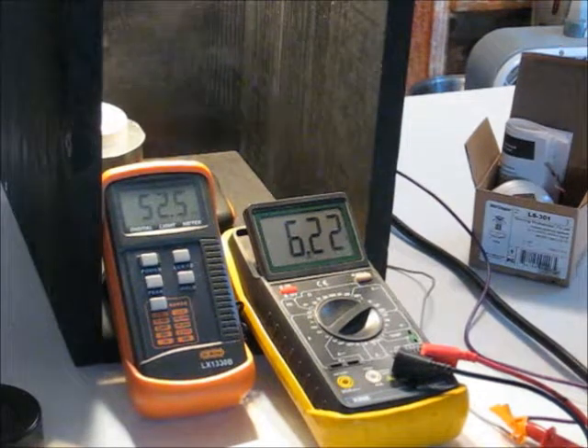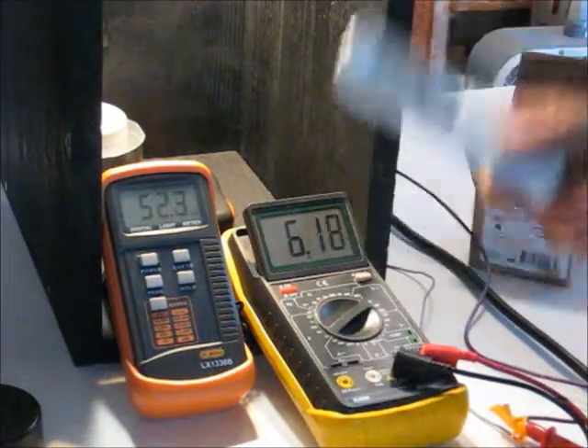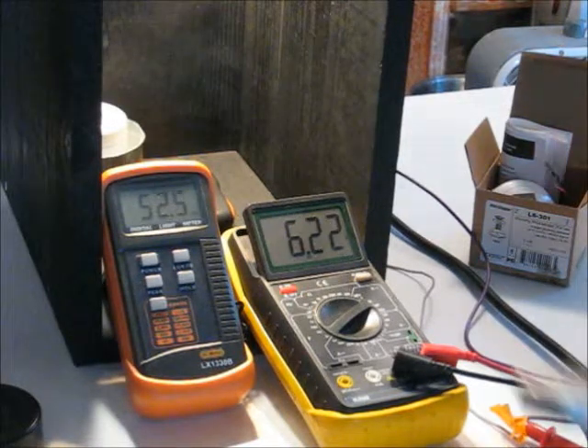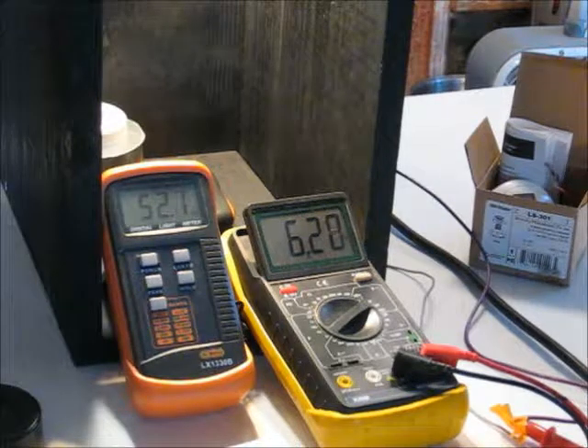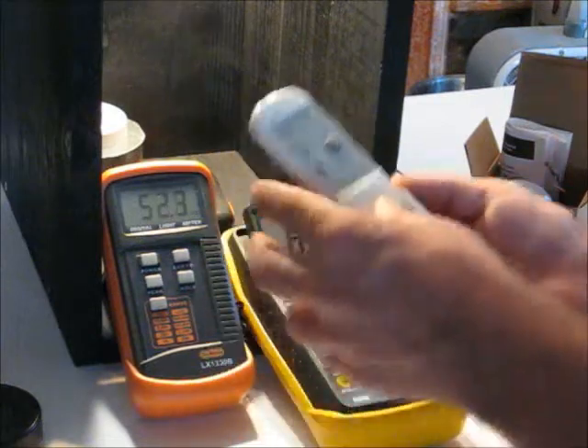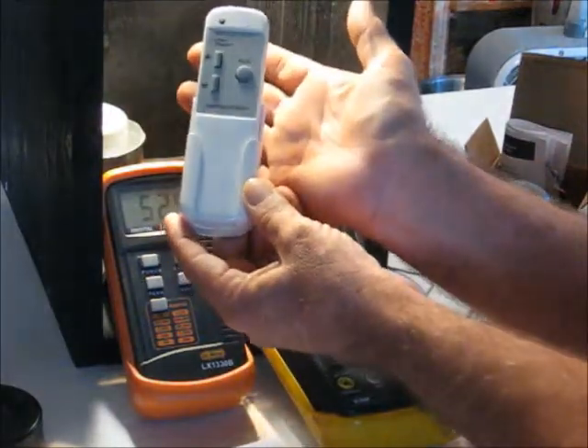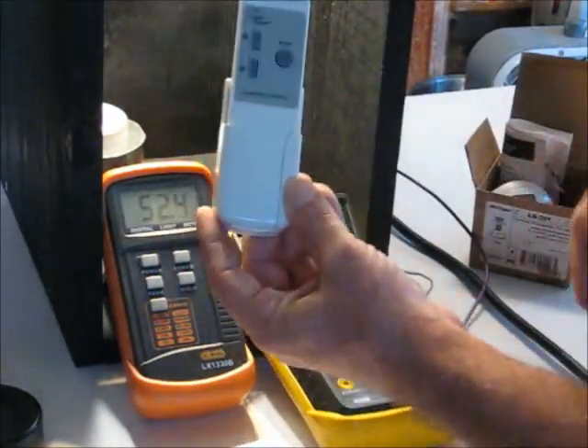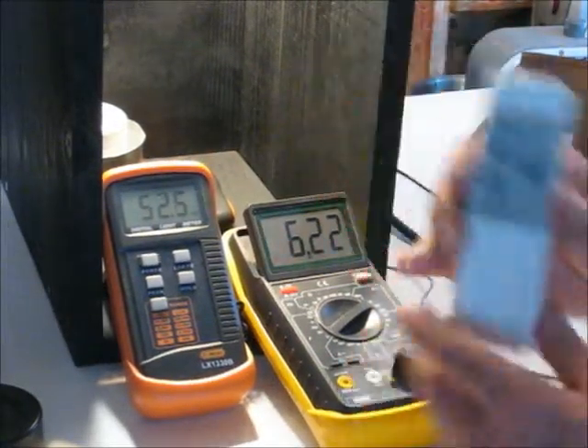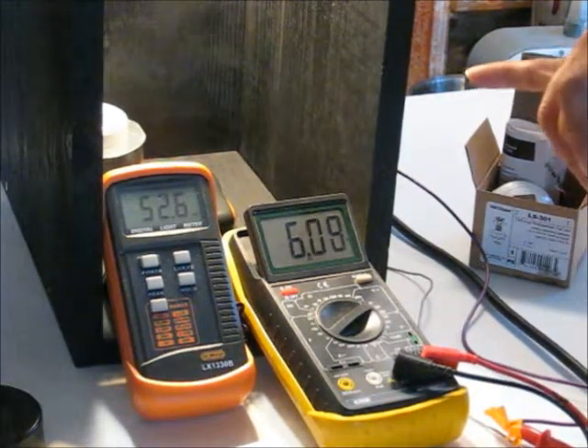So you could think of this as being a temporary override on the sensor, on the daylighting system, provided you cut the power to the sensor with the area control. And then your area control would just be basically a plain old toggle switch. However, if you're required to have multi-level control, you would need this handheld as well, and it comes with a little holster so that you can make it readily accessible if it's required that this be in the area with the lighting. So, as far as I'm concerned, this device is probably good to go wherever you need one.